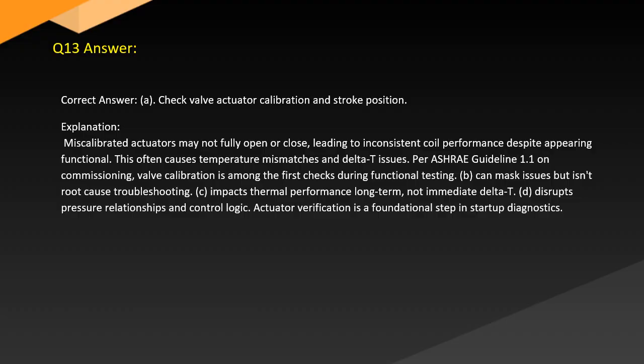Answer. Correct answer: A. Check valve actuator calibration and stroke position. Explanation. Miscalibrated actuators may not fully open or close, leading to inconsistent coil performance despite appearing functional. This often causes temperature mismatches and delta-T issues. Per ASHRAE Guideline 1.1 on commissioning, valve calibration is among the first checks during functional testing. B can mask issues but isn't root cause troubleshooting. C impacts thermal performance long-term, not immediate delta-T. D disrupts pressure relationships and control logic. Actuator verification is a foundational step in startup diagnostics.